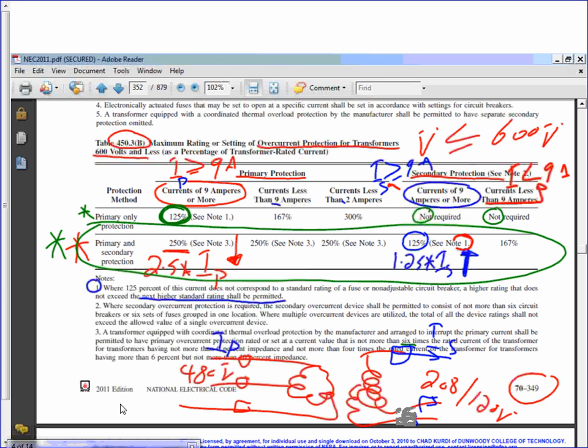Yes? Karen? Good? So on the test, guys, you're expected to go to your code book, highlight that table, and use it. Okay, so that's your 125%. One more time. You're going to see me multiplying by 2.5 here because of 250%. You're going to see me multiplying on the secondary side by 1.25 because of the 125%. And I'm going to be multiplying by 2.5 on the primary because of the 250%. Okay? Here's your primary, here's your secondary current, here's your primary current. Both of them have protection. Can you guys see that?